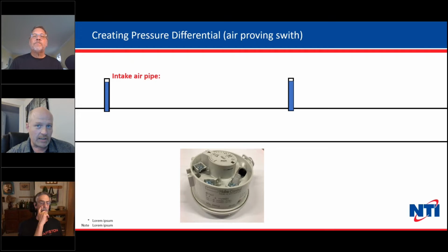Now, we still do this on the LX products. So if it's got a white Huba switch like this, it actually gets tripped by creating a pressure difference. So what I've represented here is an air intake pipe with two pressure tappings. The little blue lines in these pressure tappings are supposed to represent pressure.